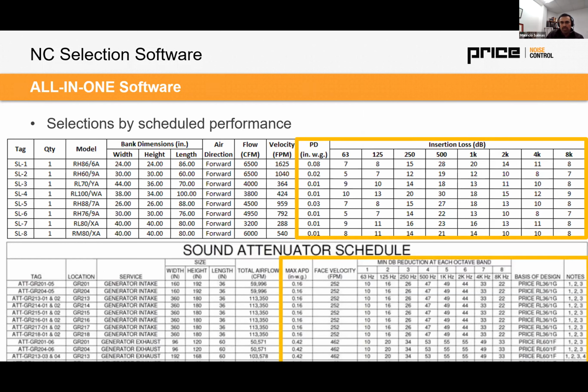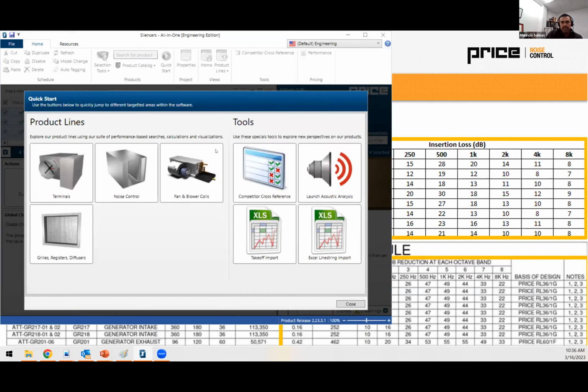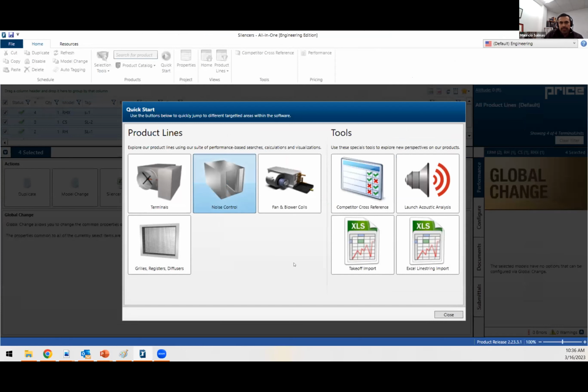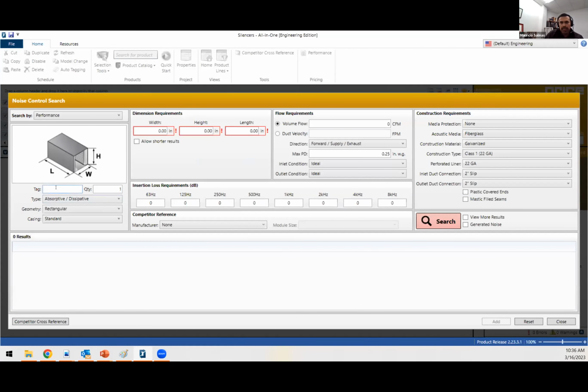You want to put all that information in, and the way to do that in the software is you go to the noise control icon. And when you open that, the layout is a bit different than other products in all-in-one. You can add your tags easily. You could have your silencer type, so absorptive, most applications, schools, commercial, whenever you have a more stringent requirement where you have to keep the air quality clean, you have a polymer film bagged option, which is going to prevent erosion of the media into the airstream. If you have dimensions on the schedule, you can do that.